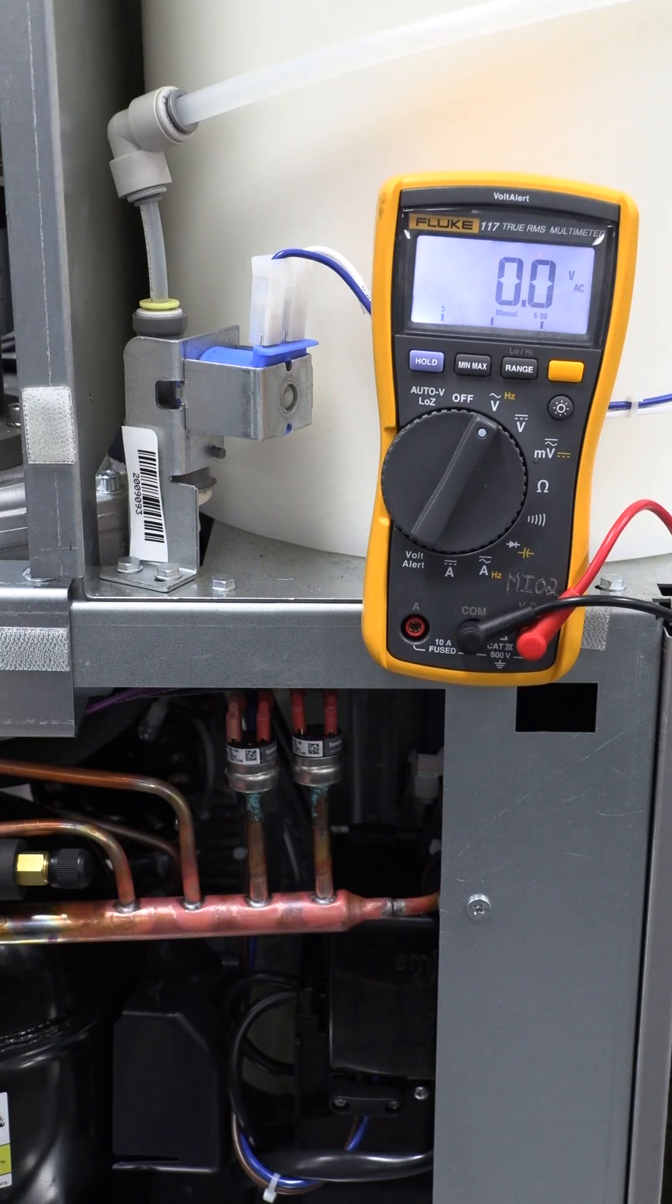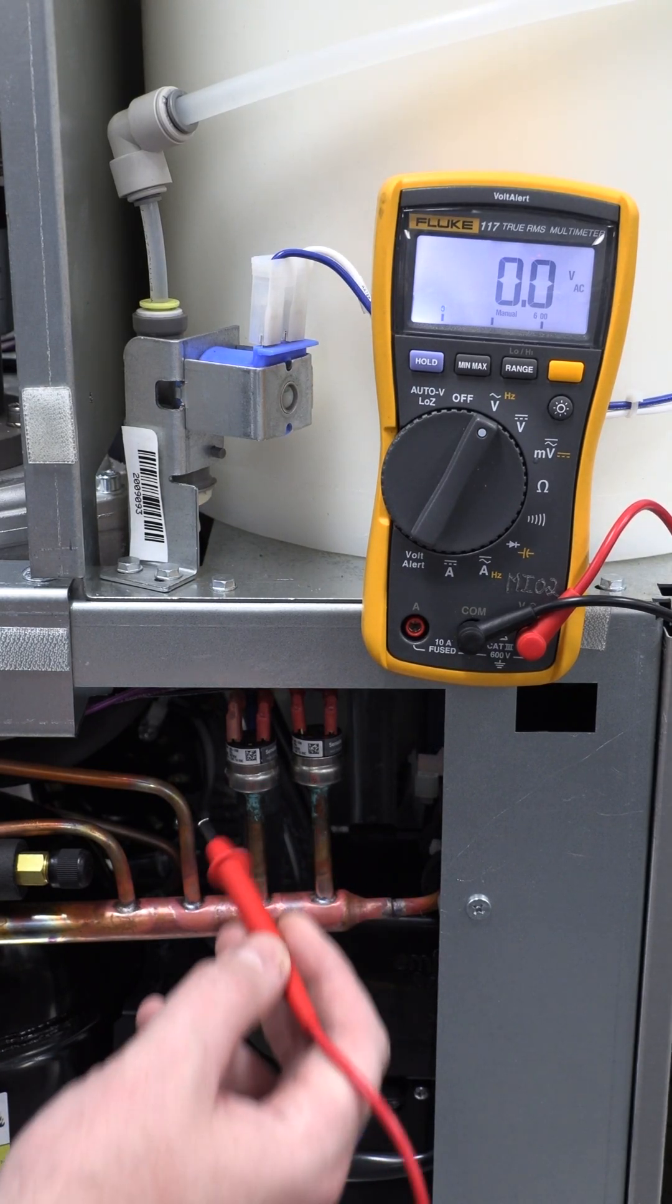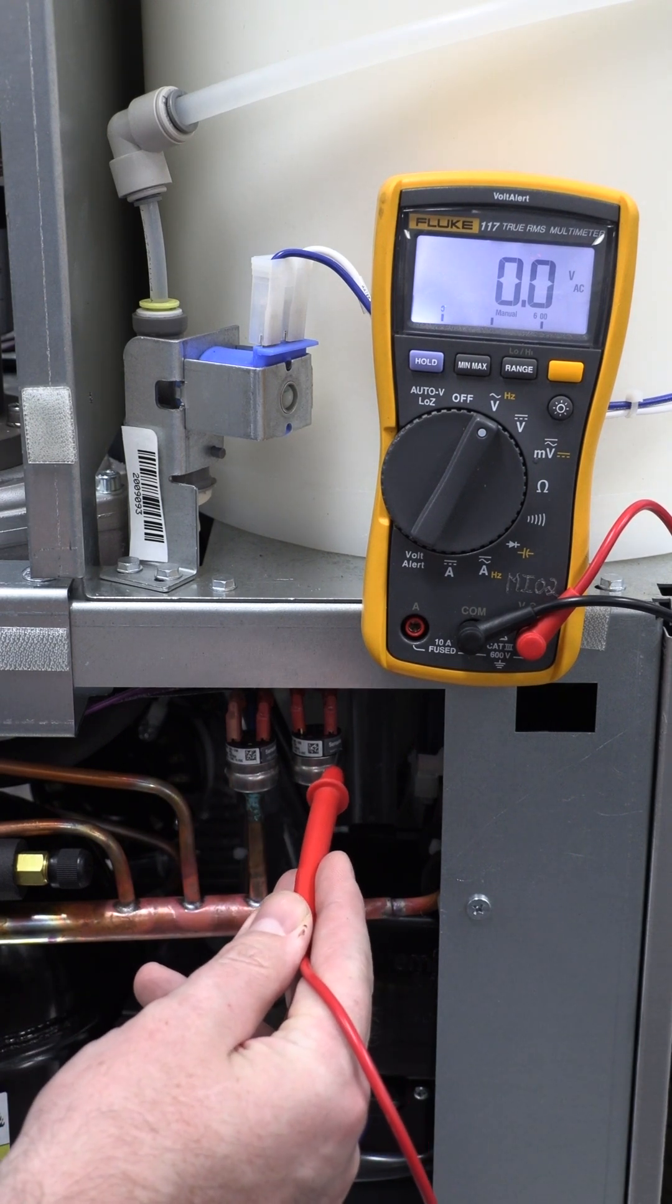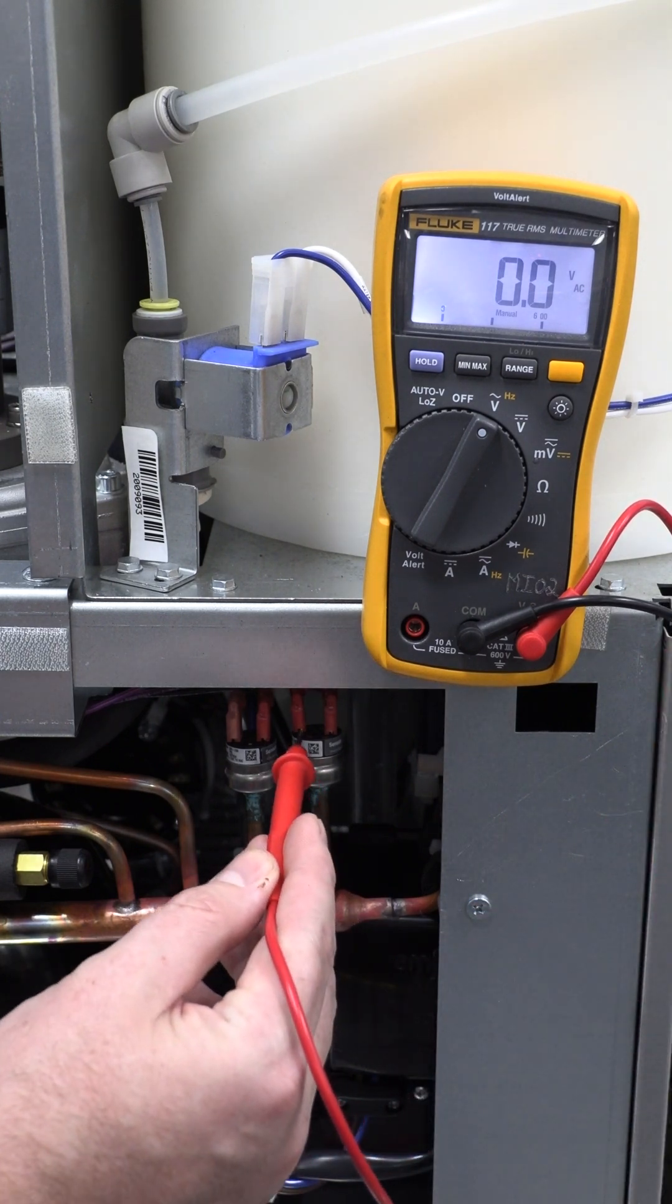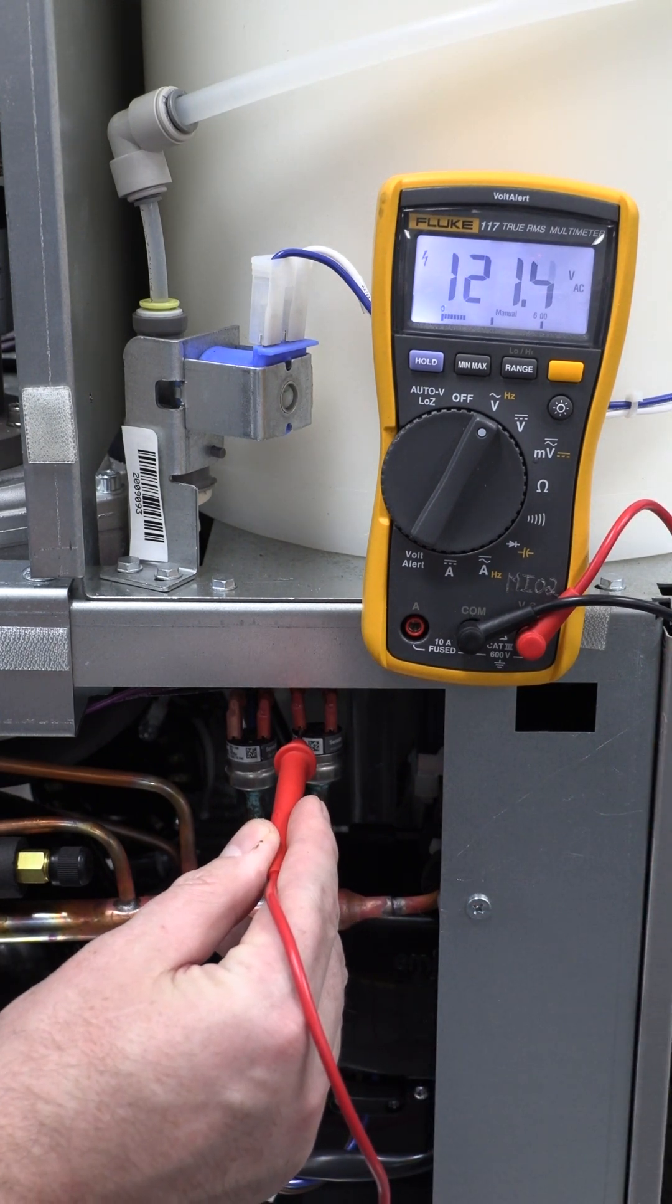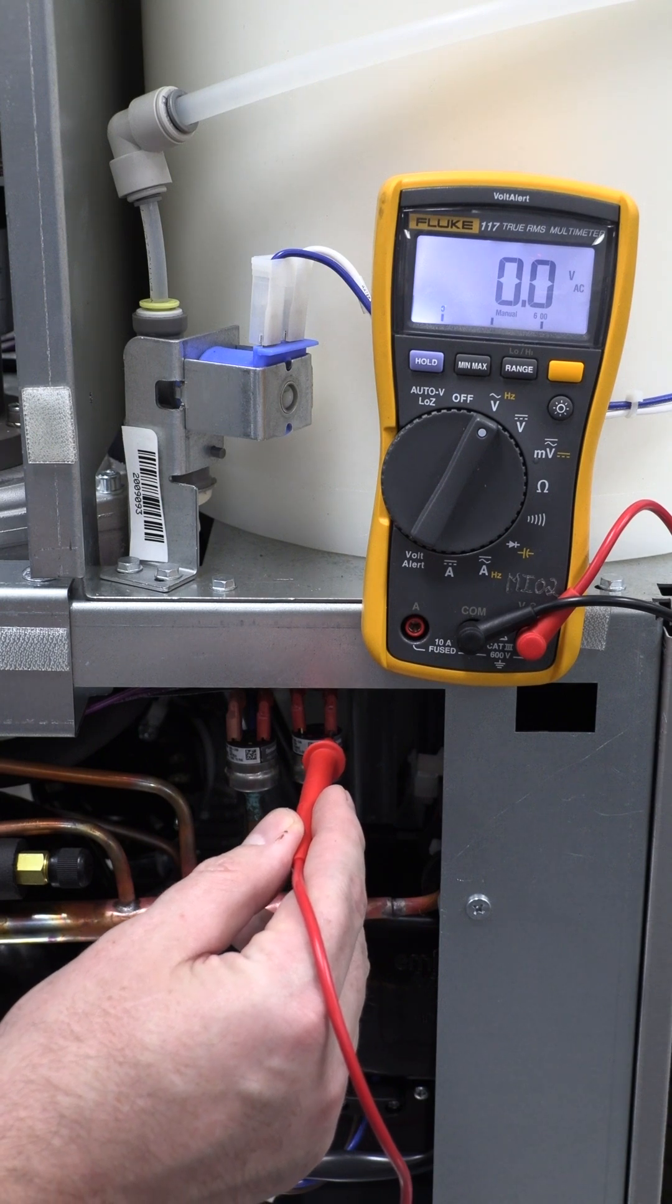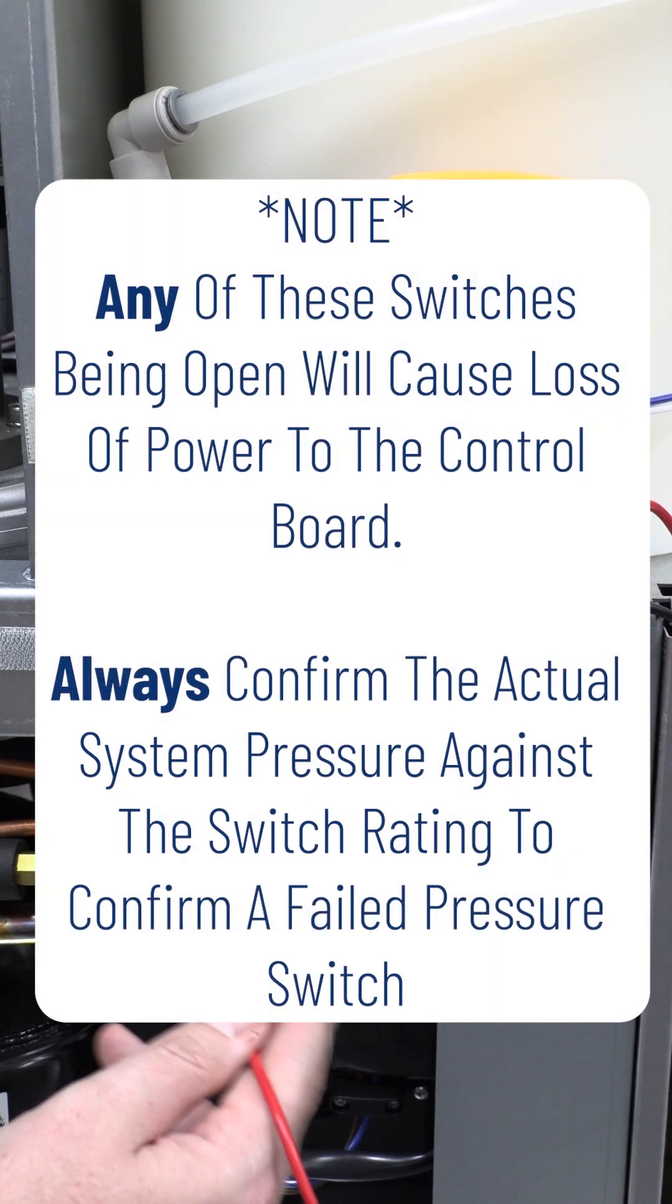Now we're over here looking at the compressor discharge line and you'll see two switches here. The one on the left is your fan cycle switch. The one on the right is your high pressure cutout. Again, my black wire is still connected to the neutral on the other side. If you see here, I have good voltage coming into the switch and an open circuit coming out of the switch. So today we have a failed high pressure cutout causing no power to come to that board.